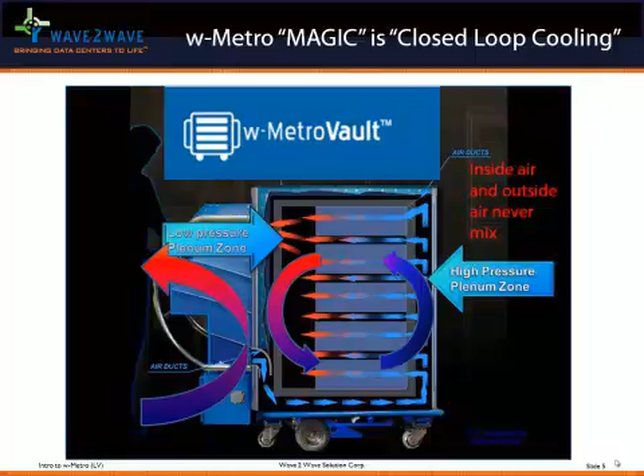Inside air and outside air never mix. Our products are either NEMA 12 or NEMA 4 compliant, meaning they're dustproof, waterproof, and totally sealed up, protected from the elements. The AC unit on the left is cooled by ambient air coming from the bottom and going across the cooling coils to cool down. It's a simple but patented process, and a very efficient way to cool your equipment, minimizing wasted air used to cool effectively empty space.